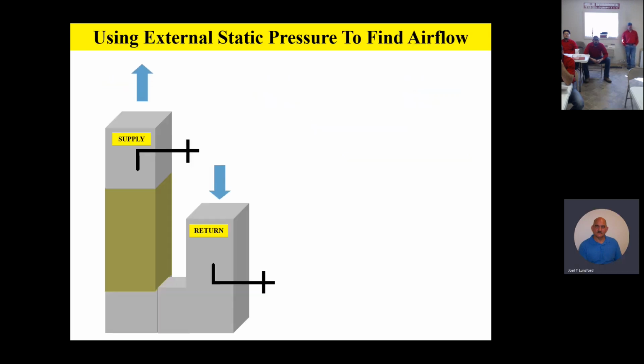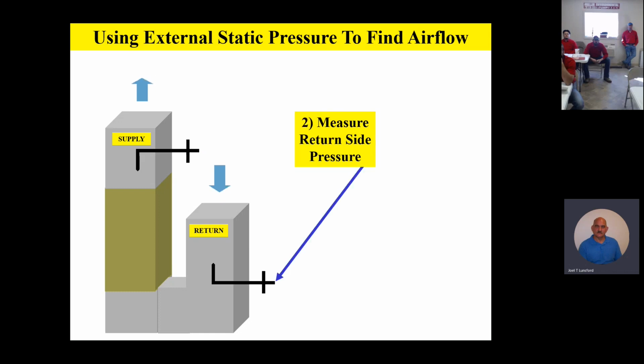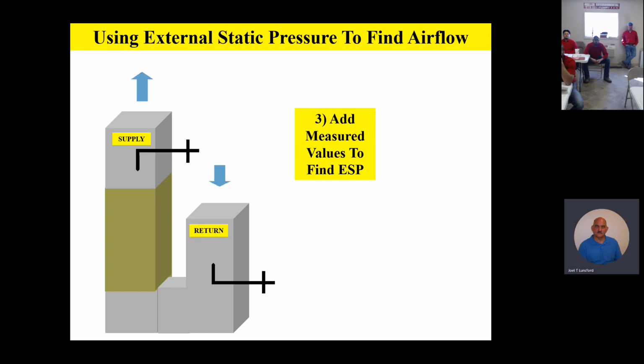And then in this graphic example, you'll see that I'm going to take that static pressure probe and just drill a hole in the ductwork, and slide that static pressure probe in, and I'm going to look at the supply and the return static pressure. So we read supply side static on the supply, return side static on the return, and then we add those two values up to get external static pressure. And this is how the airflow charts work on our factory airflow charts.